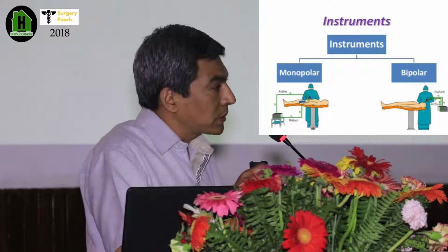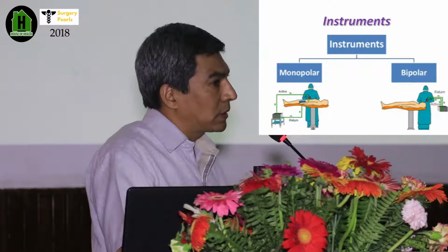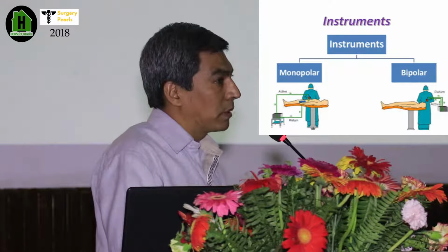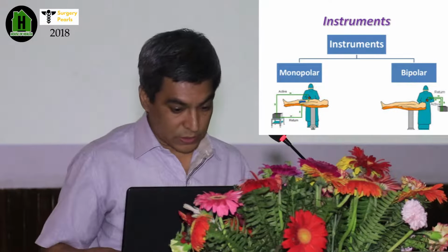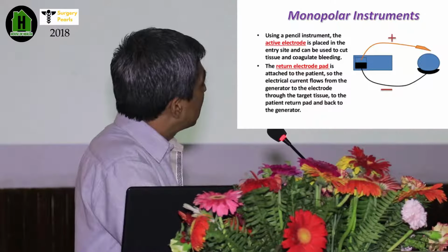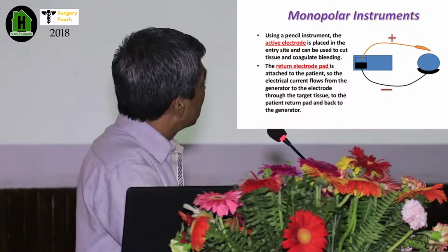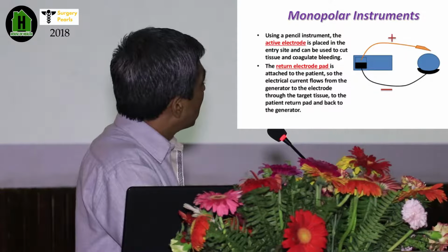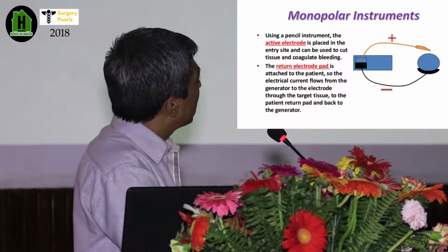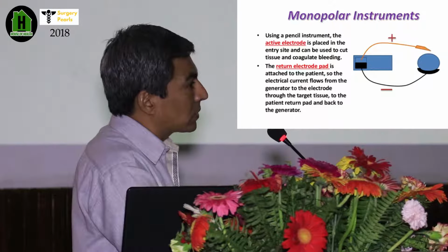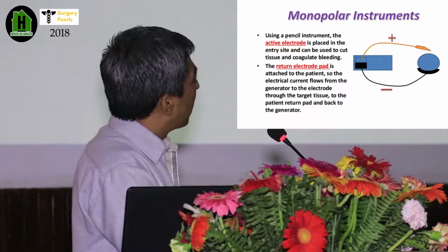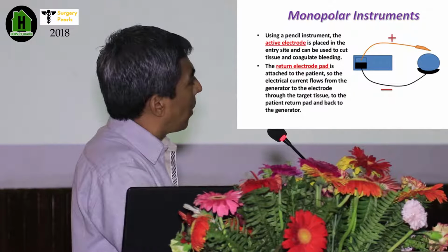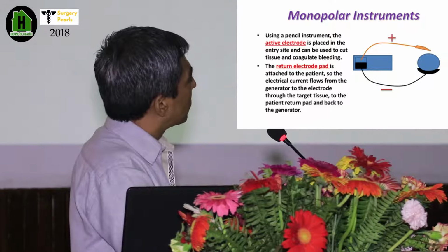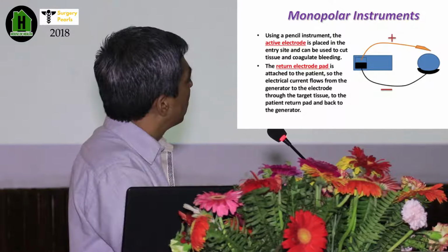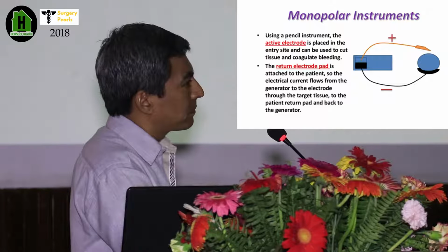However, the coagulation and the amount of heat generation, everything is almost similar between the mono and the bipolar. So we'll come in. In case of monopolar, this is the patient, this is the active electrode, this is the passive electrode, this is the electric generator. Whatever electricity is generated by this generator will be transmitted by the active electrode and delivered to the tissue. And after completion of this job, all the electricity, all the electrons given by the active electrode must come back to the generator through this passive electrode.